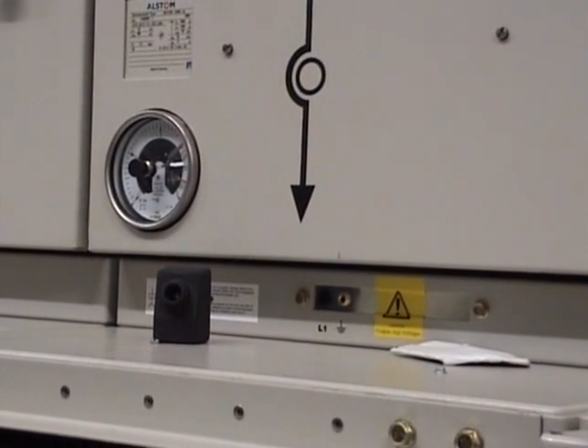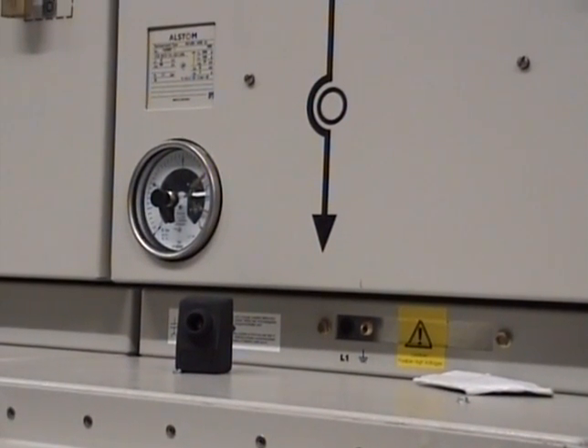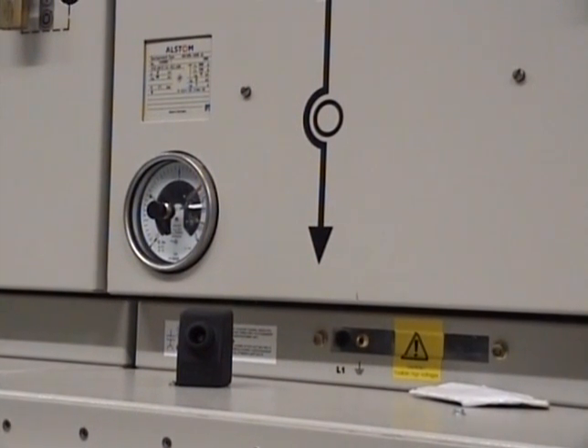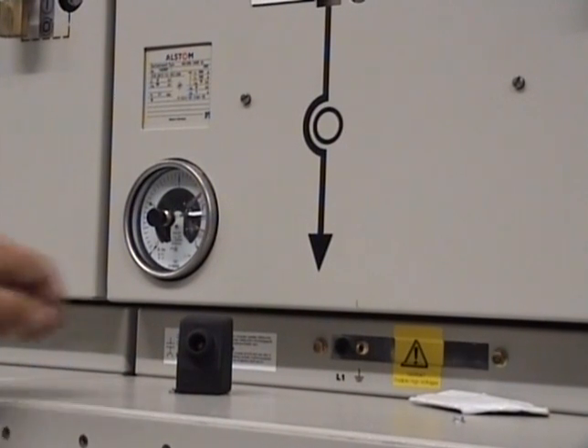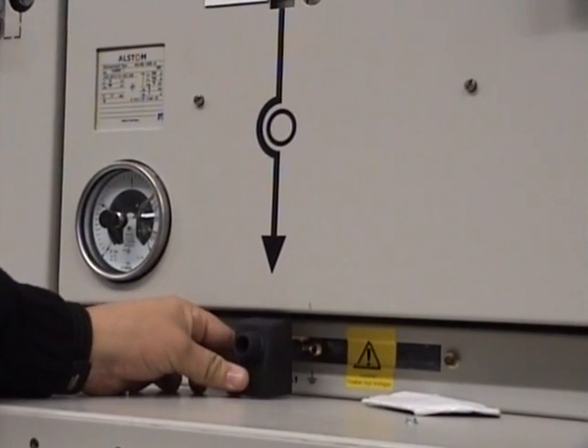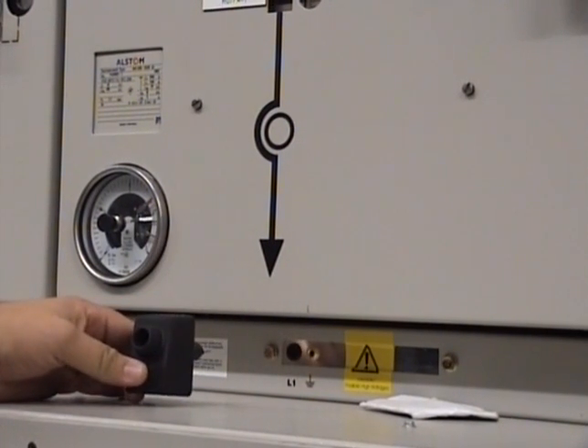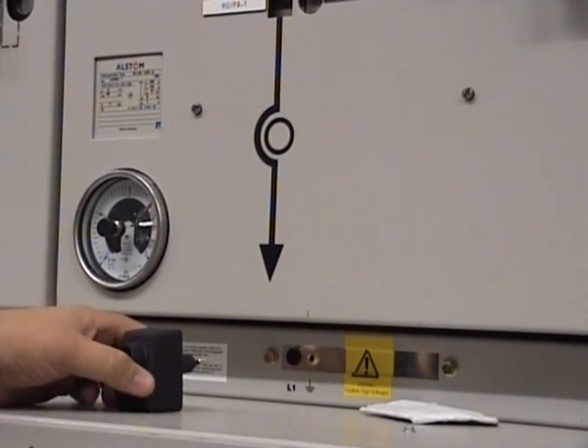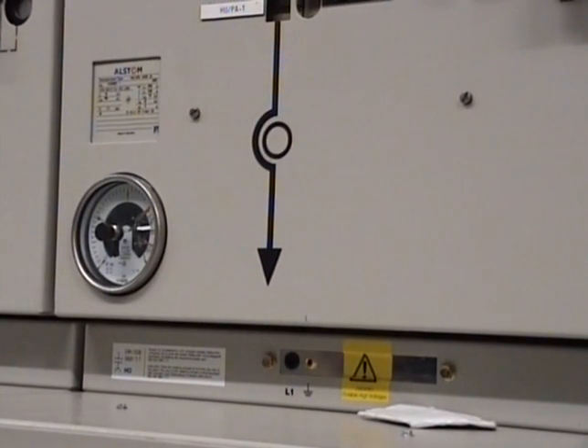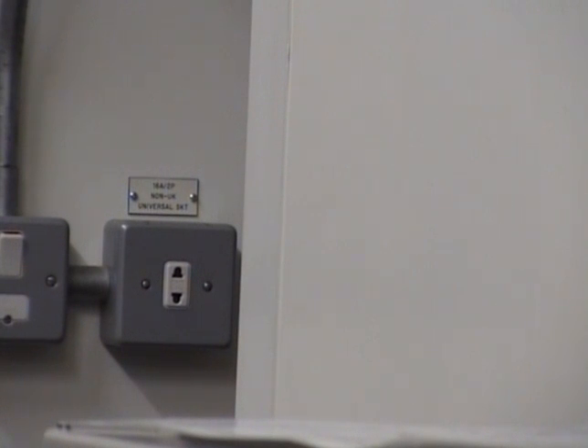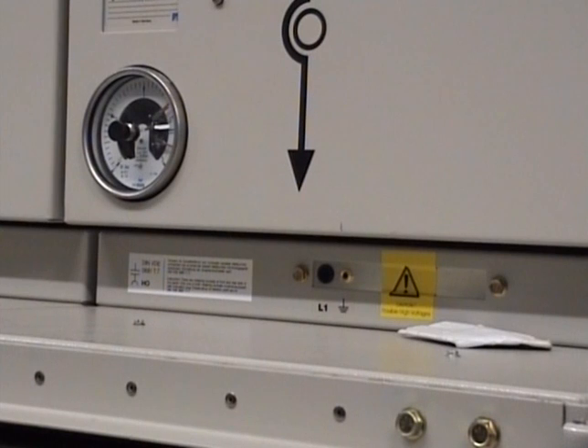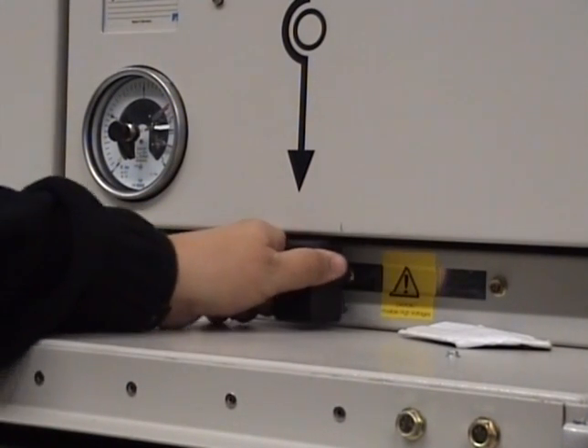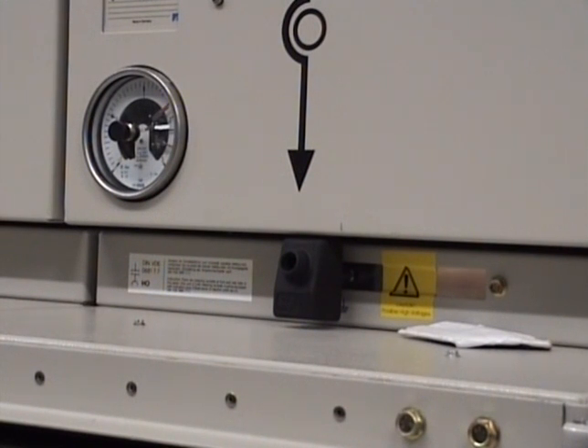We test the cable by means of the cable test device on the lower left. We are next going to test the cable by means of the test lamp, which fits into a socket which is connected to a detector in close proximity to the cable. But first we have to make a test to ensure that the testing device works. We either test the tester by applying it to adjacent live equipment, or in the absence of this we have a mains derived test socket on the wall. We plug the tester in, we see that it illuminates, which confirms that it is working correctly. We now apply the tester and confirm the cable is dead.